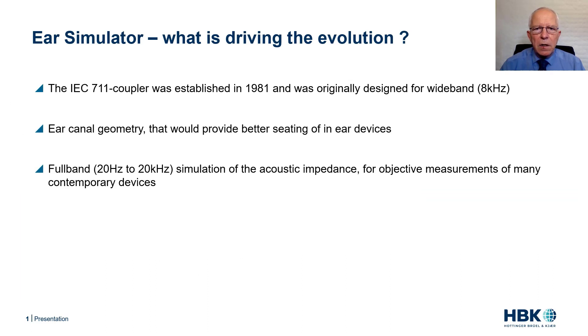For the last decade, the evolution of ear simulators has been driven by the increasing need for more realistic simulation of the acoustic impedance. Realizing that the 711 coupler was established in the beginning of the 1980s — where wideband performance was considered well suited for most applications — can be an issue when measuring on contemporary devices in super wideband and fullband applications. When it comes to accommodating a realistic seating of in-ear devices, the cylindrical ear canal geometry of the 711 coupler can be less suited for such devices.